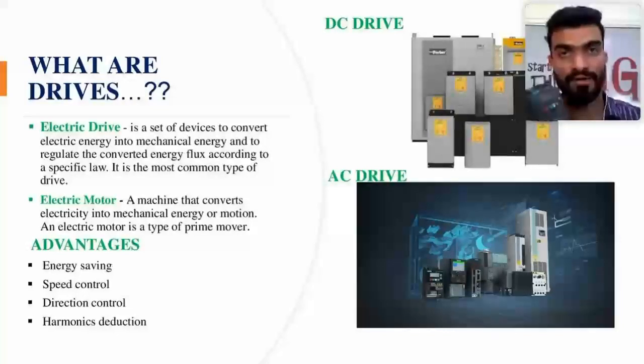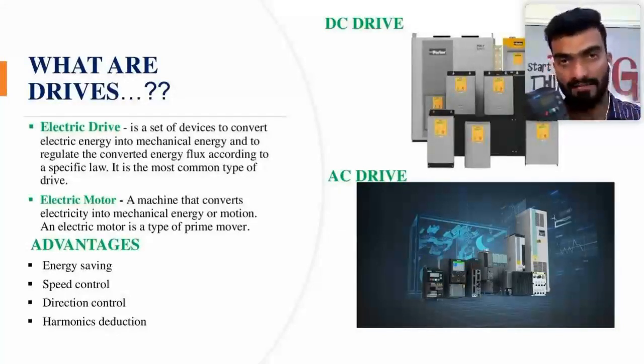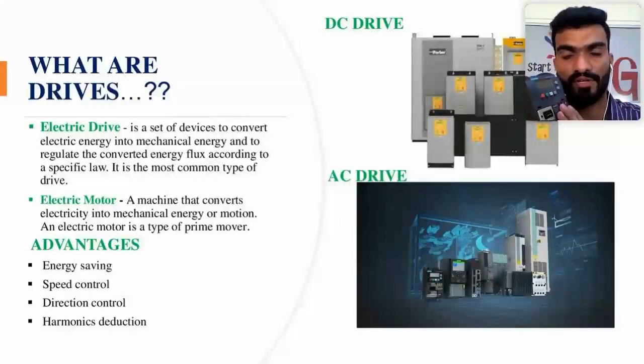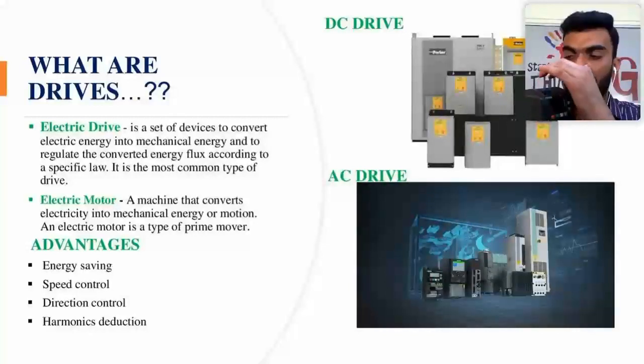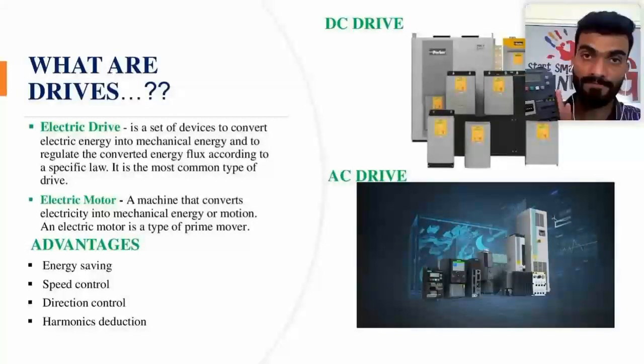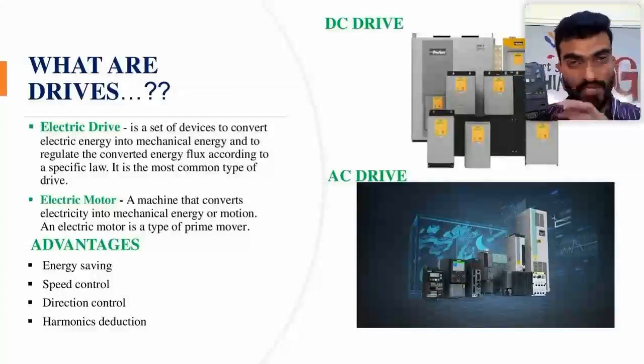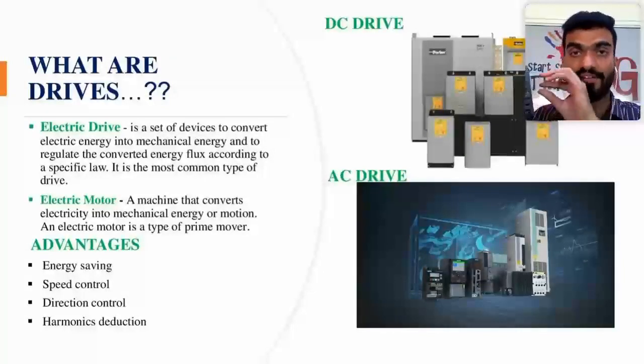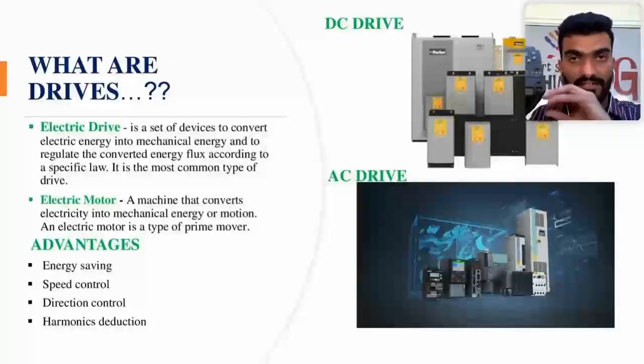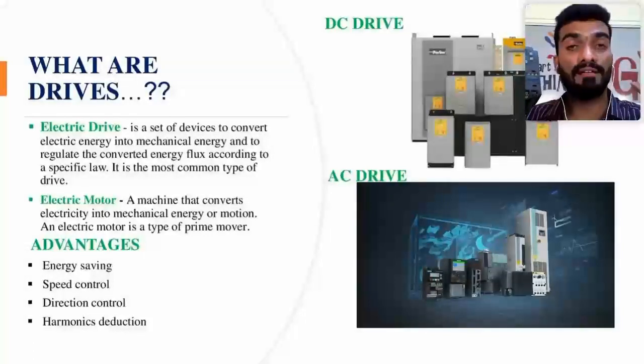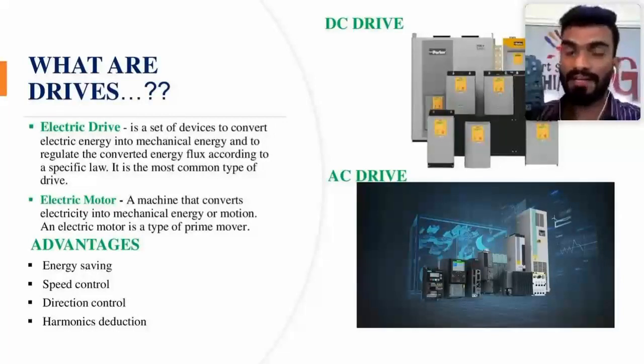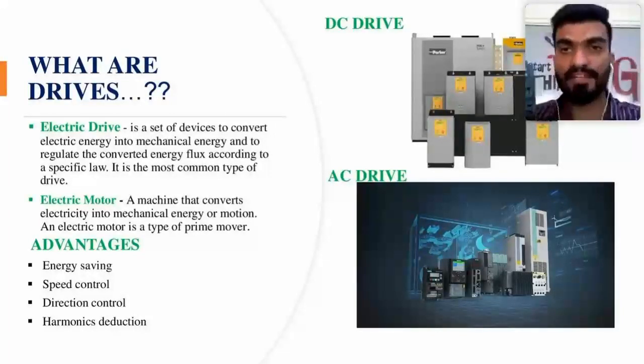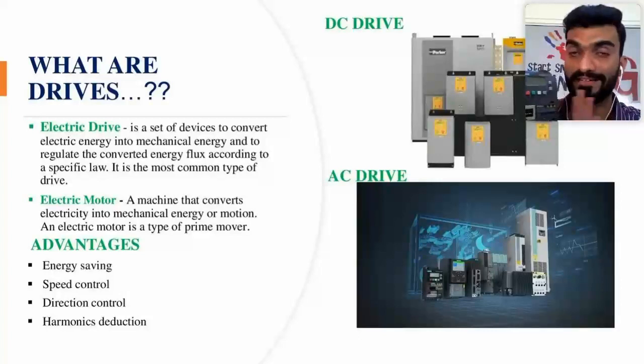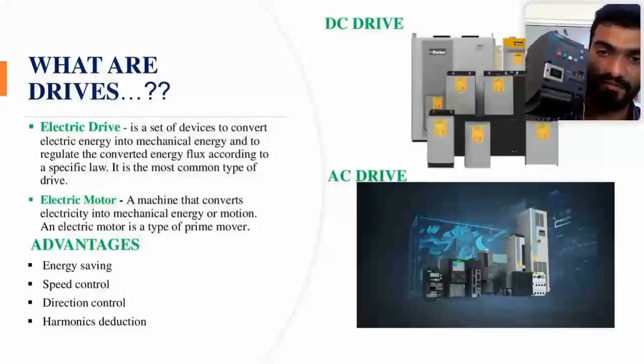Whatever the motor full load current is, it will be reduced when you connect through a drive, because the drive will convert AC current into DC current, and based on the motor load, the DC is again converted to AC, and it will be given to the motor based on the end requirement, based on the load, I can say. So the motor won't always take full current, whereby your energy is saved. So these are the advantages of VFD.